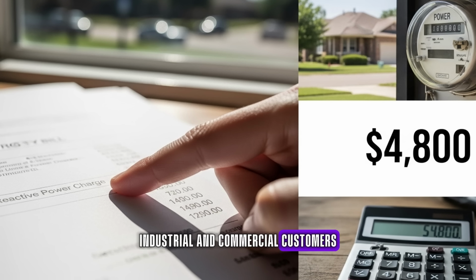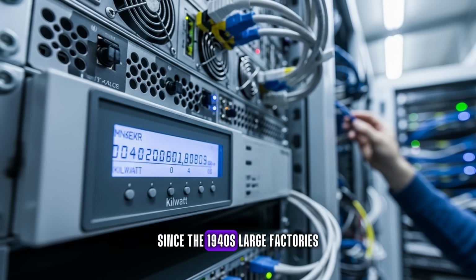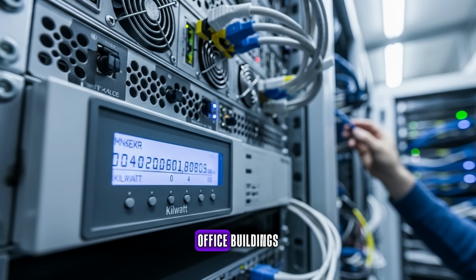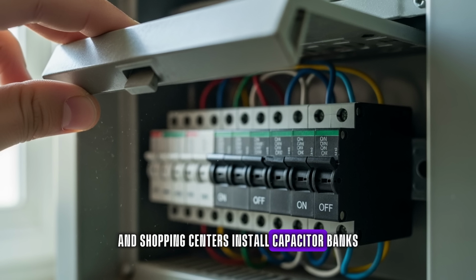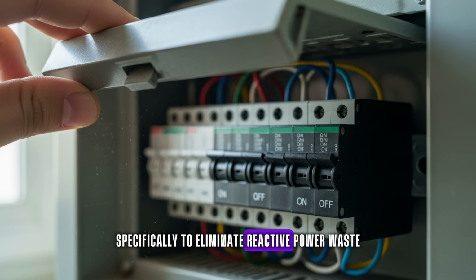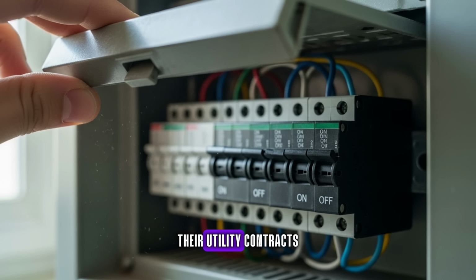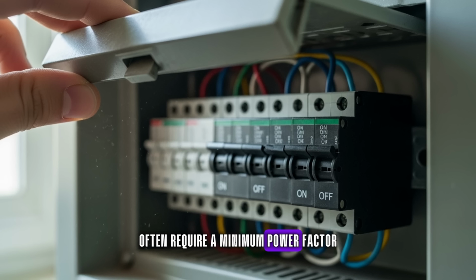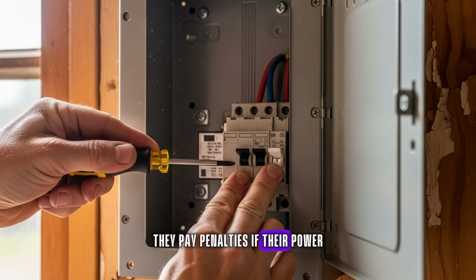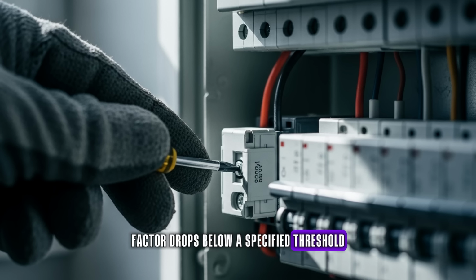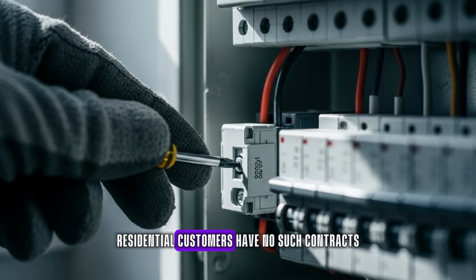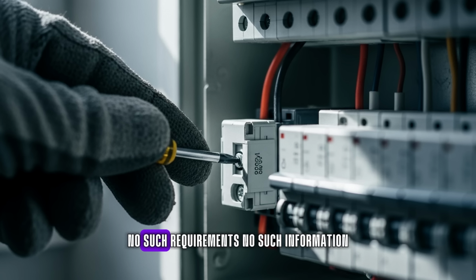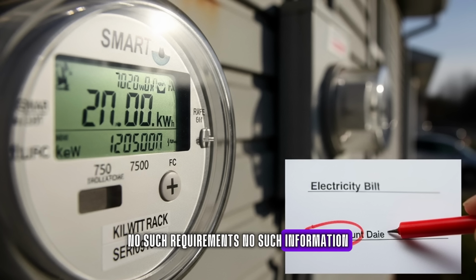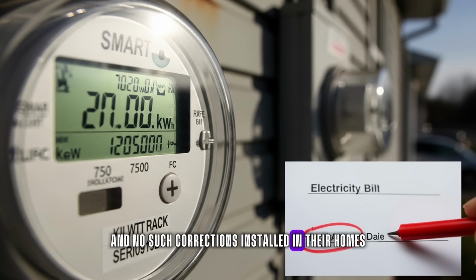Industrial and commercial customers have known about power factor correction since the 1940s. Large factories, office buildings, and shopping centers install capacitor banks specifically to eliminate reactive power waste. Their utility contracts often require a minimum power factor. They pay penalties if their power factor drops below a specified threshold. Residential customers have no such contracts, no such requirements, no such information, and no such corrections installed in their homes.